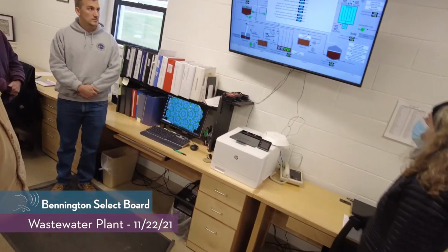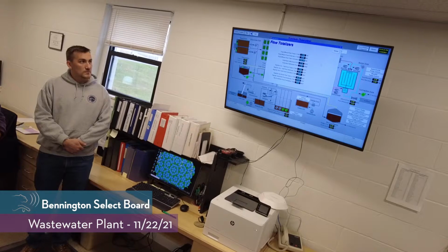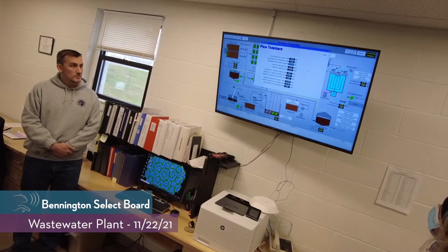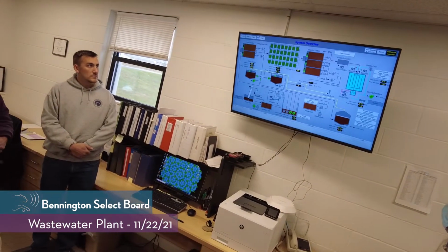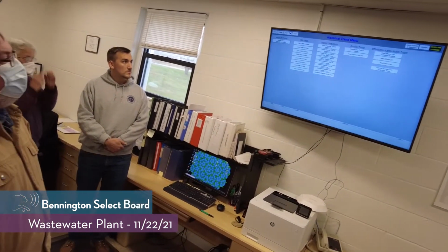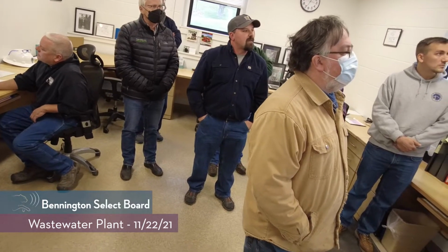With SCADA, it also gives us a lot of charting, so we can go back from when we turned SCADA on and see all the flows and what happened, seeing trends of different things and what's not working. For example, we realized one of our main raw sewage pumps wasn't efficient—every time it ran, another one would run too, so it was really just idling along doing nothing. That one went out to be rebuilt, and it's actually out right now.